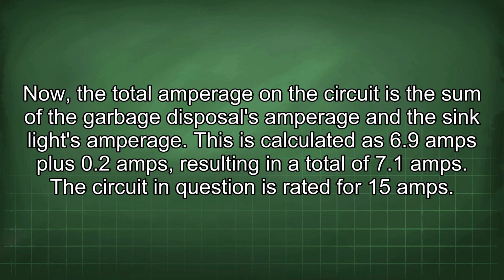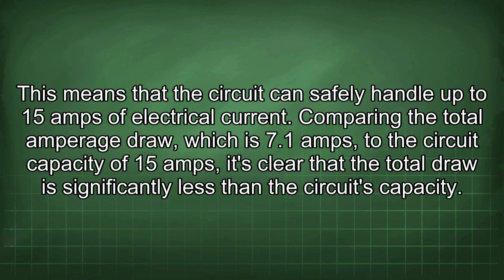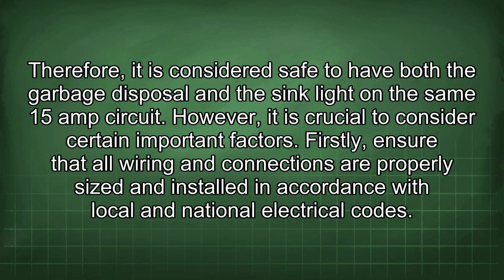The circuit in question is rated for 15 amps. This means that the circuit can safely handle up to 15 amps of electrical current. Comparing the total amperage draw, which is 7.1 amps, to the circuit capacity of 15 amps, it's clear that the total draw is significantly less than the circuit's capacity. Therefore, it is considered safe to have both the garbage disposal and the sink light in the same 15 amp circuit. However, it is crucial to consider certain important factors.